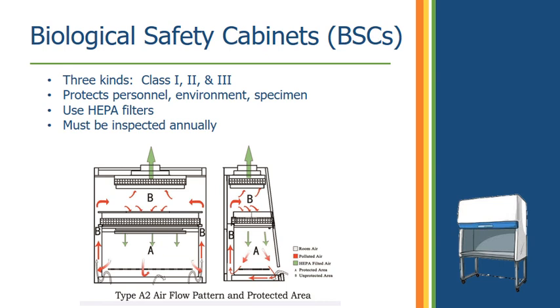The airflow for these cabinets is very carefully calculated to be the most efficient for removing possible contaminants from the air and preventing recirculation back into the room. If your grate is covered with papers and the airflow gets disrupted, you are putting yourself and your coworkers at increased risk from aerosols generated inside the cabinet. Your lecture manual has a chart outlining all the different types of cabinets and the differences between them. Next time you're around yours, take a look — what class do you have, when was it last certified, and is there anything on the grate that needs to be moved?